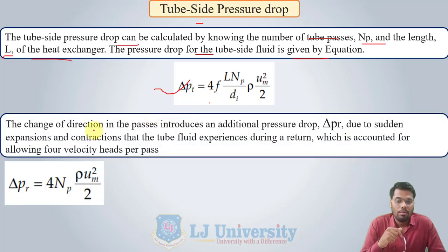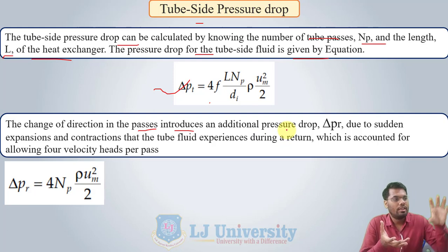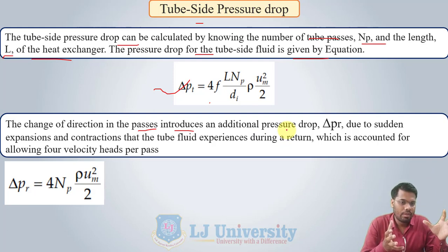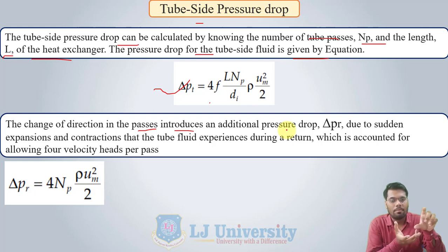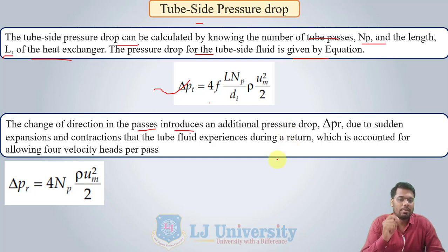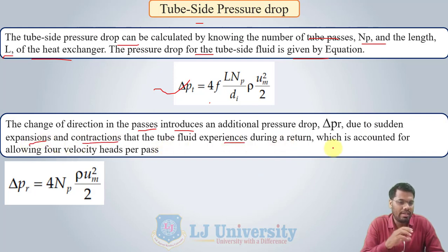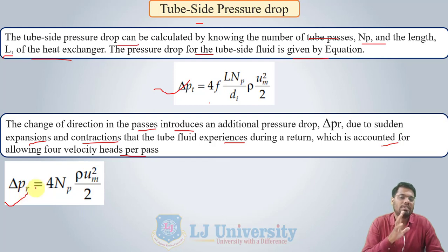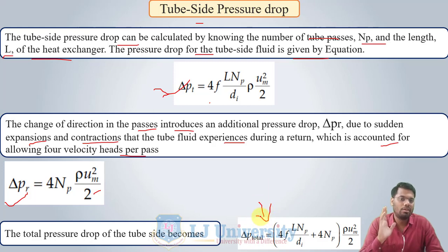There is an additional pressure drop because of the change of direction in the passes. In a shell and tube heat exchanger, when the fluid enters the shell, there is a larger area; when it enters the tube, there is a contraction of area. After passing one pass, the fluid again experiences a larger area — expansion. Due to this contraction and expansion, there is an additional pressure drop. This sudden expansion and contraction that the tube fluid experiences during return is accounted for by allowing four velocity heads per pass. The summation of these two equations gives the total tube side pressure drop.